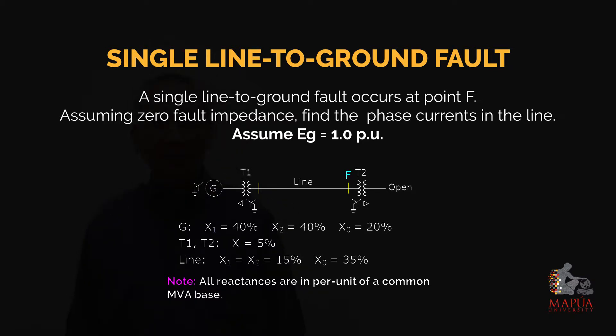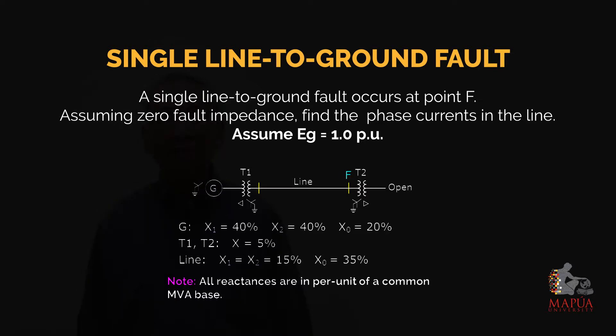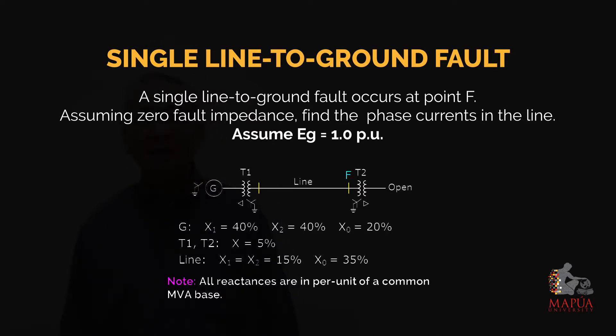These are the given data. For the generator: the positive sequence reactance is 40%, the negative sequence reactance is 40%, and the zero sequence reactance is 20%. For transformers T1 and T2, the reactance is 5% each. For the transmission line, the positive and negative sequence reactance is 15%, and the zero sequence reactance is 35%. Note that all reactances are in per unit on a common MVA base.